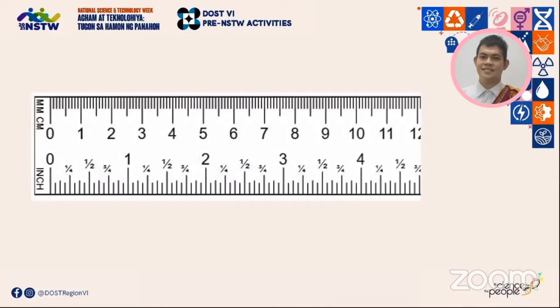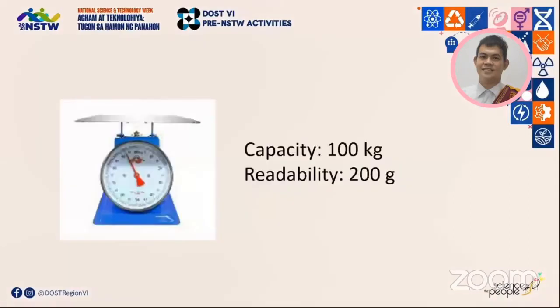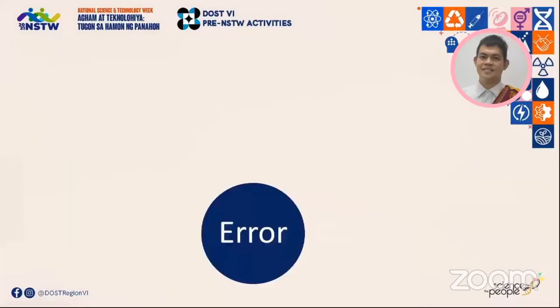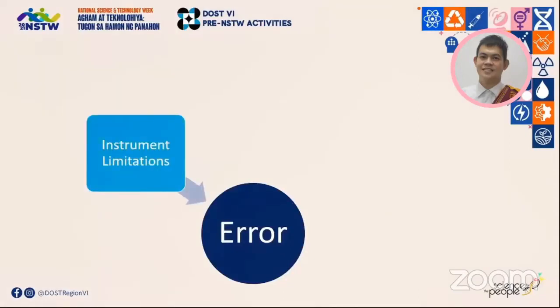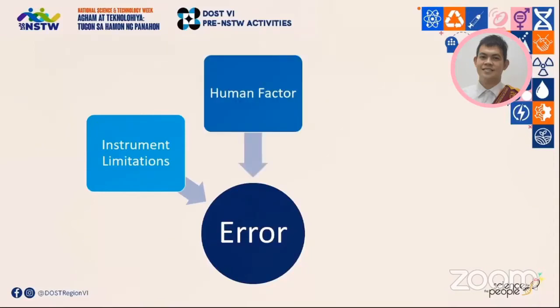Consider the case of a top-loading spring scale which has a capacity of 100 kilograms and a readability of 200 grams. The indications of this device will not be able to provide you direct information when the pointer falls in between two minor markings. At some point, you will have to make some sort of approximation or estimate. This is one possible source of error. There could be a multitude of sources of errors in a measurement. The most common ones are instrument limitations, which are due to the way these devices are designed. To err is human, as they say.